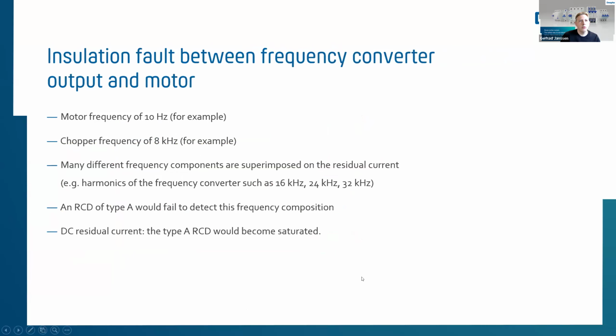Yeah, a small overview. Insulation fault between the frequency converter output and the motor. What are the reasons? Often the motor frequency is at 10 Hertz, or the chopper frequency, at 8 kilohertz, is feeding direct DC currents into the grid. So there are many different frequency components involved in those VFD drives. They're superimposed on the residual current.